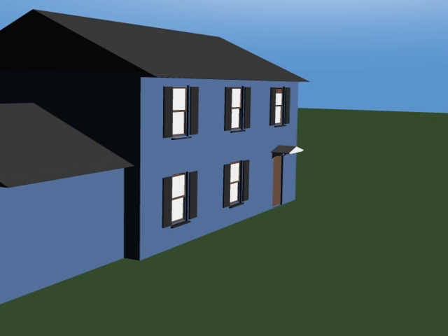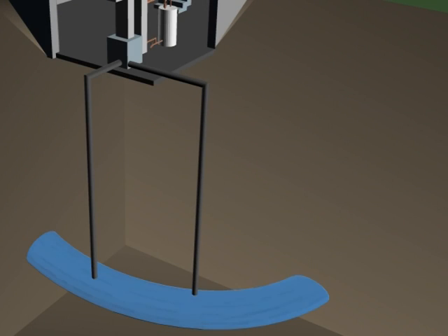In an open-loop system, on the other hand, groundwater from an aquifer well is pumped from one well and passes through the heat pump where heat is added to or extracted from it. The water is then discharged back to the aquifer or harnessed for other water management uses. Because the system's water supply and discharge are not connected underground, the loop is open.